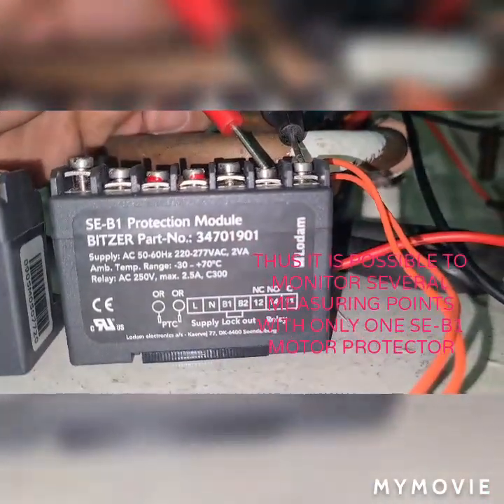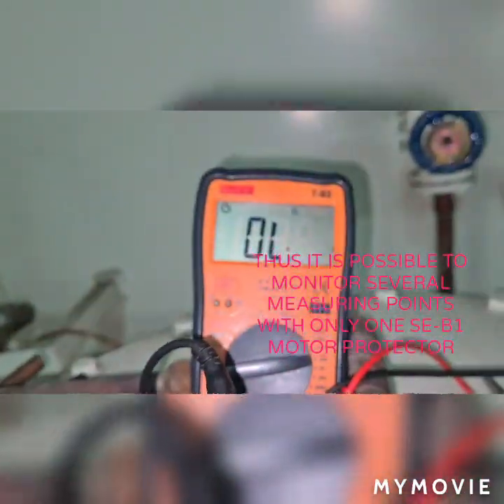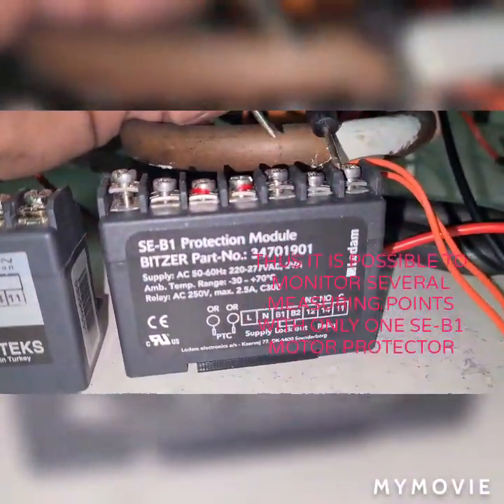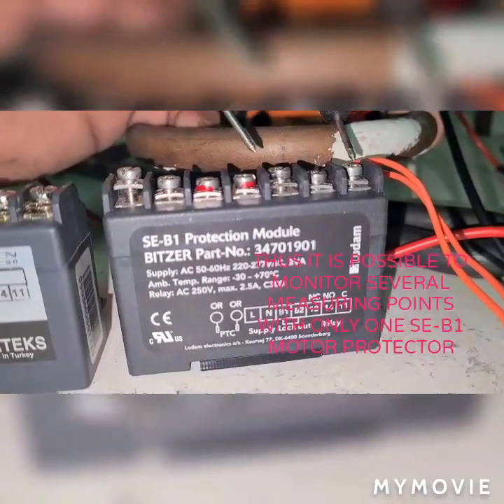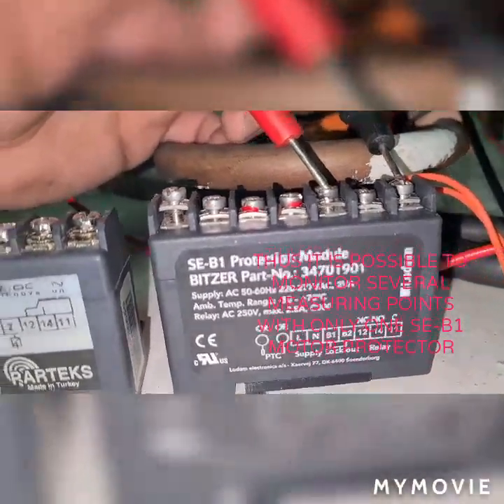If the motor coil winding exceeds a PTC resistance of about 4.5 kilo ohms, the terminal connection 11 and 12, a normally closed contact, will open to shut off the motor and protect the motor coil winding from burning.